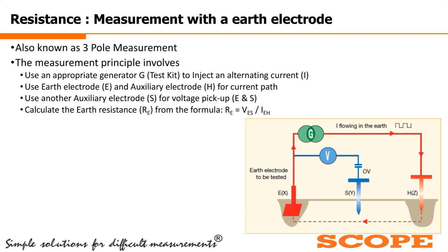Then the H terminal, the current spike or current electrode, is denoted as H. It is placed at the far end, and in between we insert the voltage electrode, which is called S. With the help of this current generator we inject the current through the H electrode, and we perform the voltage measurement through the S electrode.